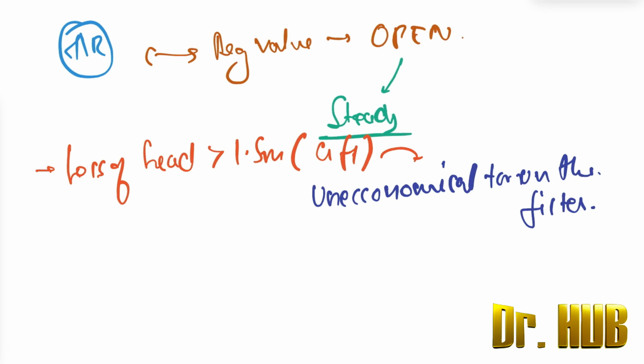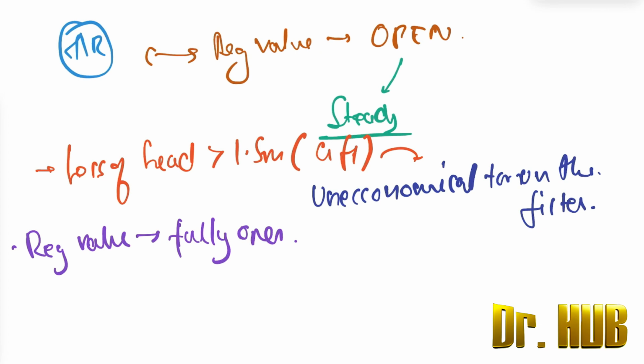And if the regulatory valve has to be kept fully open because the bed resistance is very high, then as the bed resistance is increasing, the filter needs to be cleaned.